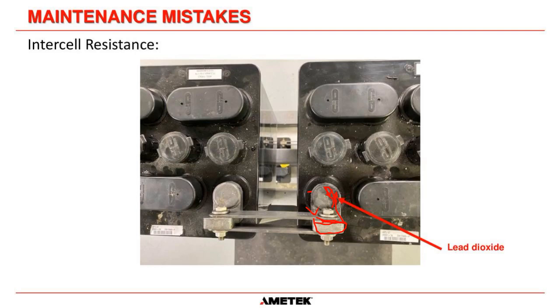So what you need to be able to do is connect your device that's measuring the intercell resistance onto the post and only the post, on both sides, and then you are measuring the whole connection resistance that way. That is the only way you are going to find a bad intercell - not internal cell, intercell - resistance.